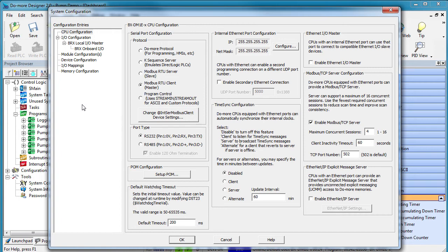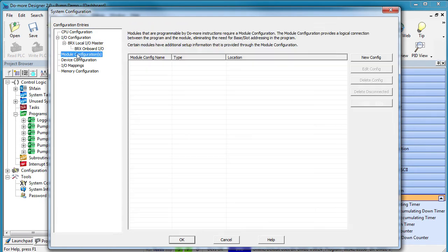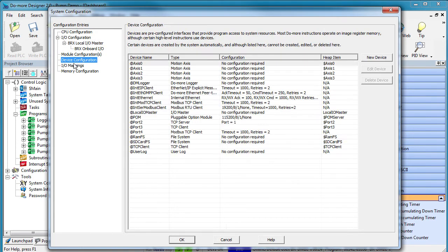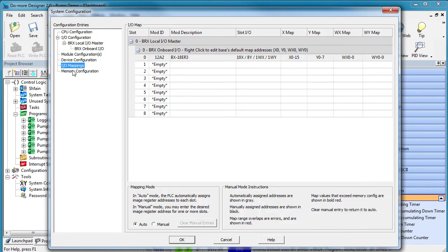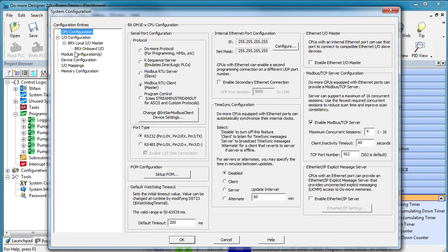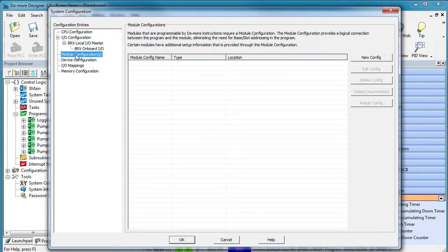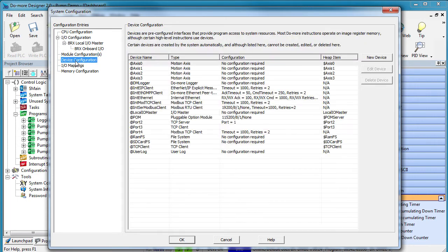The key thing to remember is you'll want to start at the top and work your way down. Why? Because each item in its configuration can affect the items below it. So first you configure the CPU, which can affect all these items. Then you configure the I/O, which can affect all these items. Then you configure the modules, then the devices, etc.